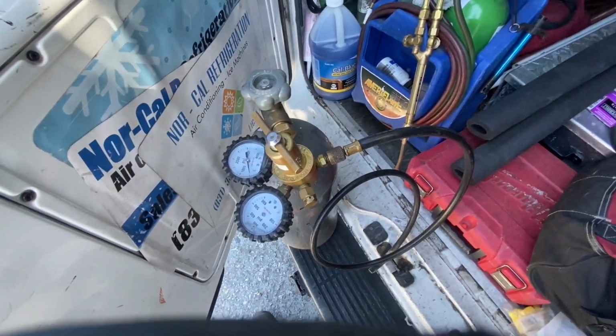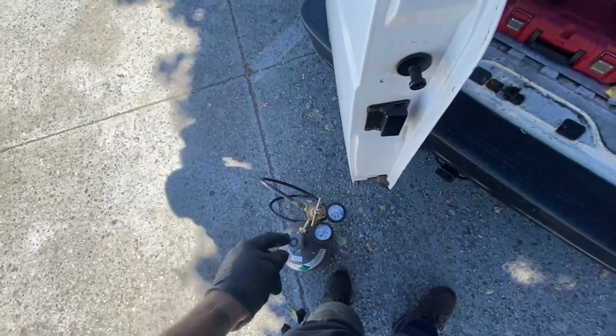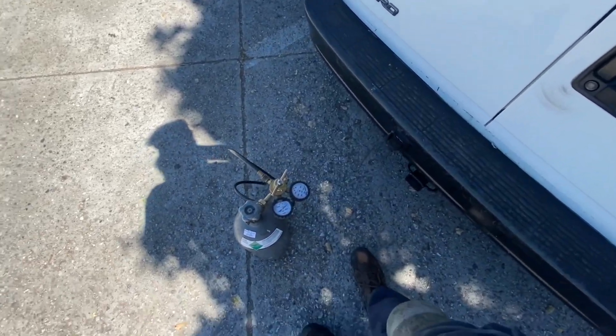All right, so the backstory on that unit is the coil was plugged up on the weekend. The thing quit cooling. It does have a high head pressure switch on it, but the coil looks impacted. We're gonna give her the old Gundy. Eat it, mama. But tons of heat coming out of that thing, so let's see if we can get it.